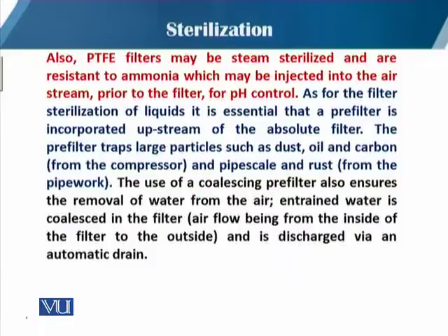Also, PTFE filters may be steam sterilized, because before using those filters we first have to steam sterilize them to ensure that they are free from contamination. They are also resistant to ammonia, which may be injected into the air stream prior to the filter for pH control. Sometimes we have to control the pH.